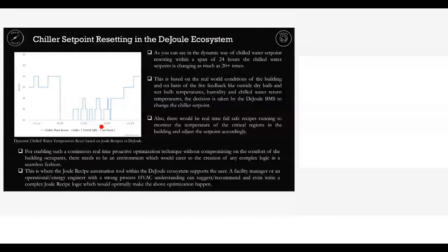So 20 times in a day, changing from say 48 degrees Fahrenheit, which is around 8.5 degrees Celsius - we use Fahrenheit because it's better to control, Celsius is more whole-numberish while this is more integer oriented. So this is at 48 degrees Fahrenheit and this is 44 degrees Fahrenheit. The temperature changes from 6.5 to 8.5 degrees Celsius over the course of 24 hours, going up and down. This is one way of saving energy real time from the chiller.